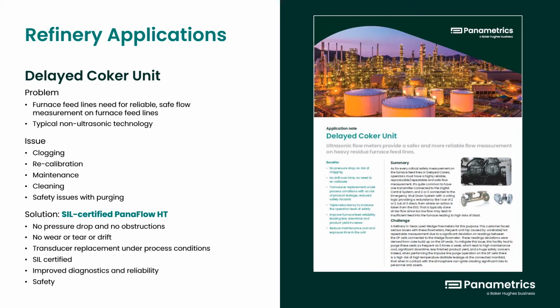The main problems with furnace feed line measurements are both reliable and safe flow measurements. Typically, non-ultrasonic flow measurement technologies have been used for these applications. The main issues for these measurements have been clogging. If these lines get clogged, they either stop feeding to the furnace and need to be shut down, or worse, have to be pigged. The absolute worst case is that the plugging in extreme conditions cause the pipe to burst, which is obviously a safety issue.